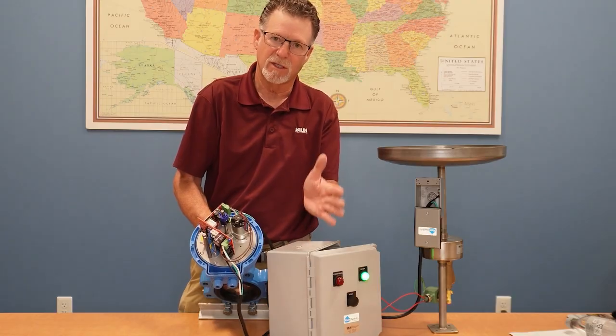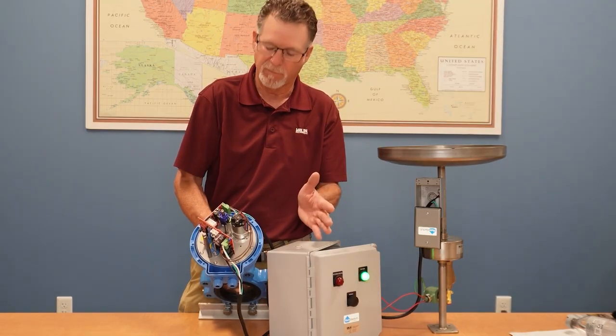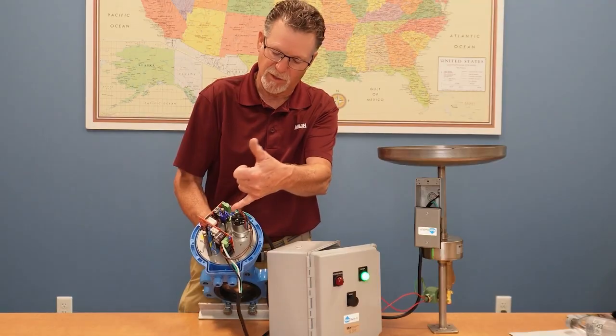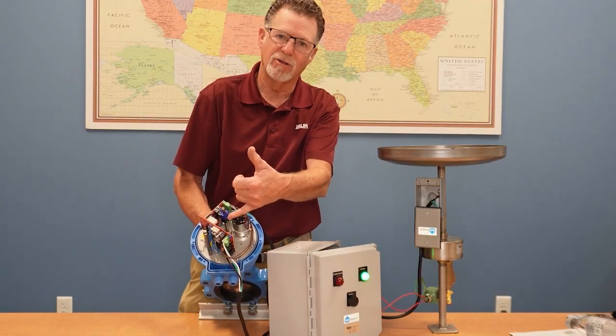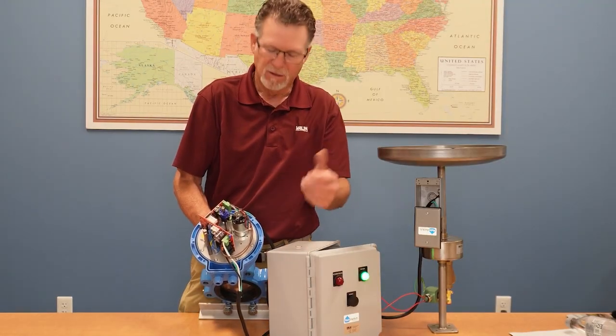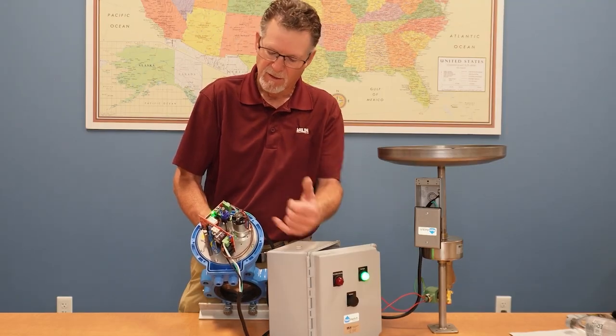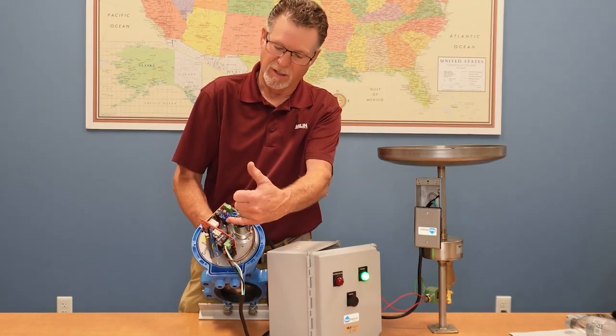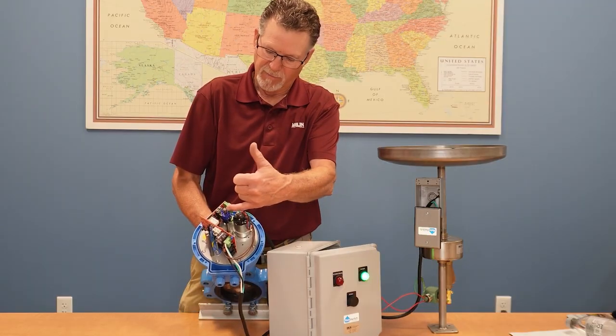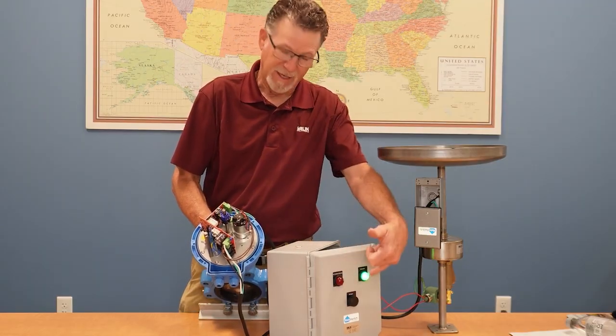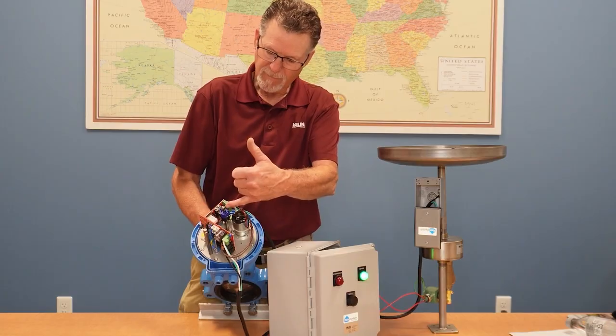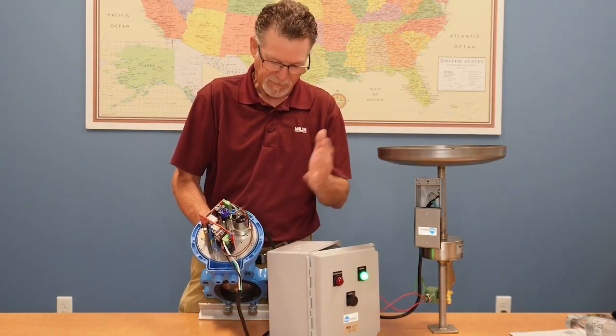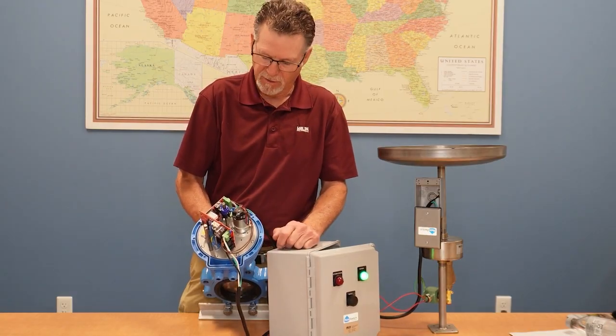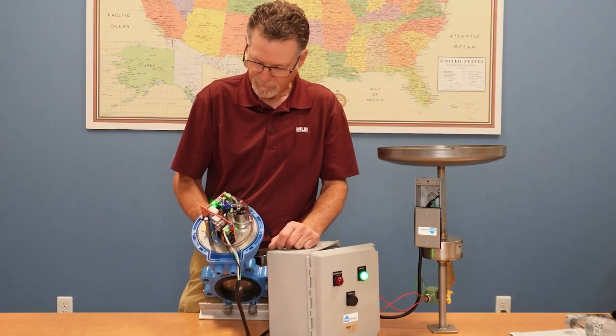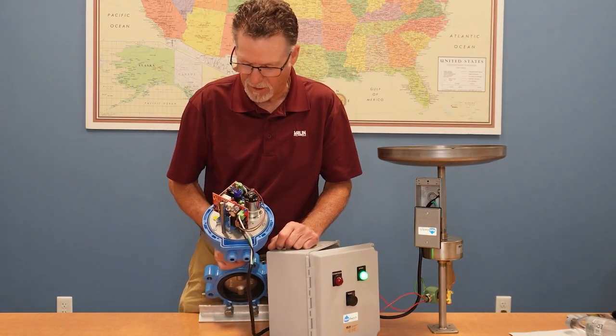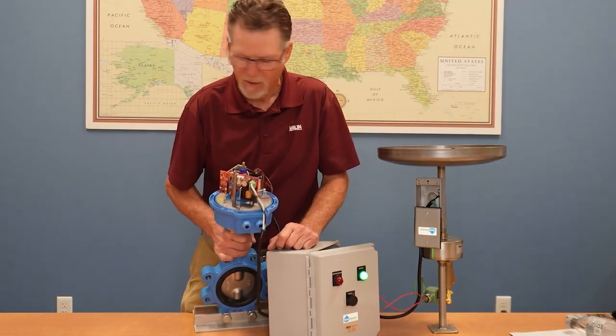As you saw, as it reached its full position, it would stop the motor, and that's being done by these limit switches. There's a small Allen there that you can adjust them if they need a little 5-degree adjustment or something. There's another set that gives you feedback, and that's what's lighting these lights. Those are also adjustable, but typically you don't need to deal with that. Other than that, there's not much else in here that you need to deal with.